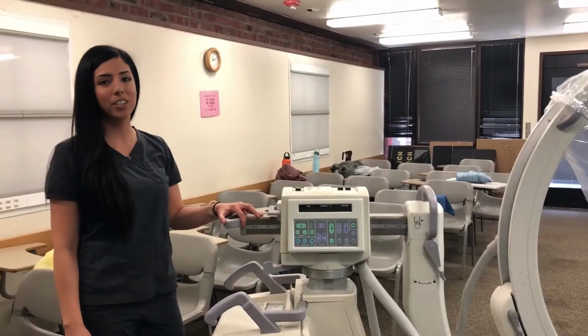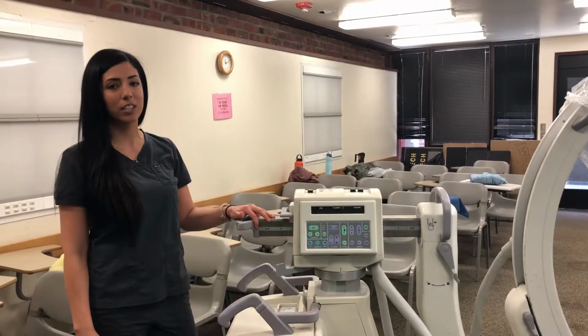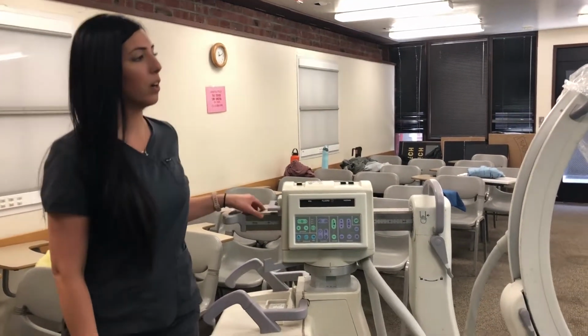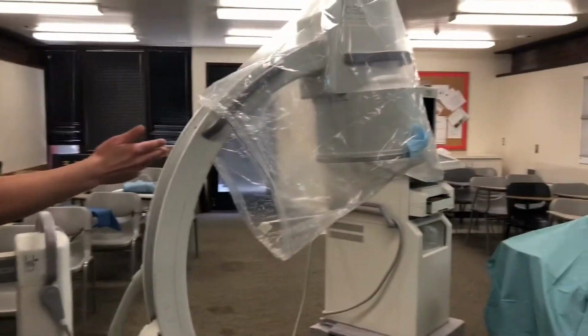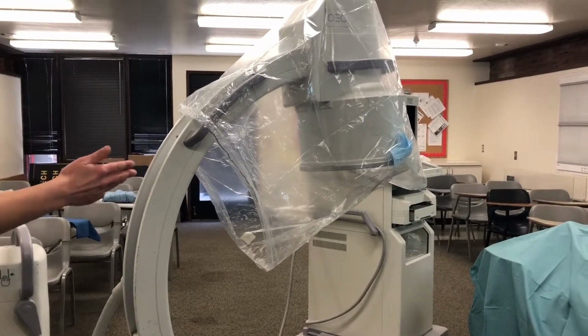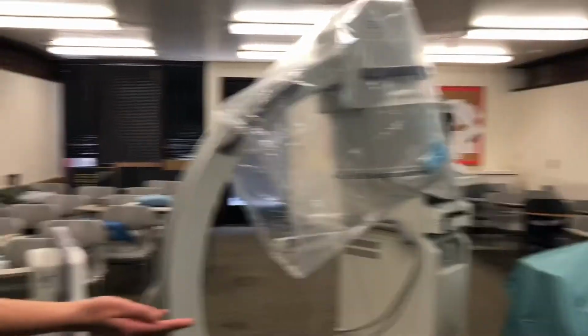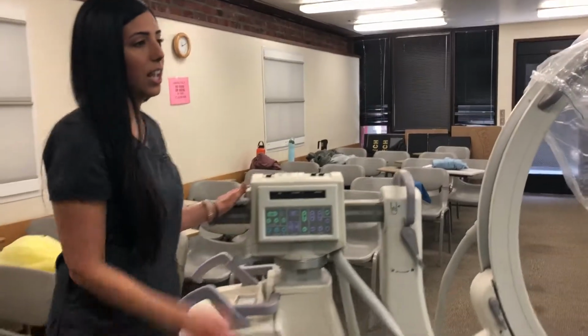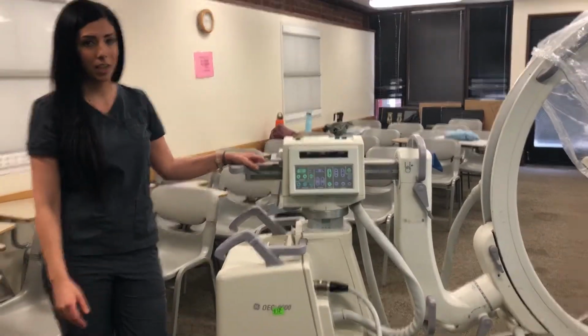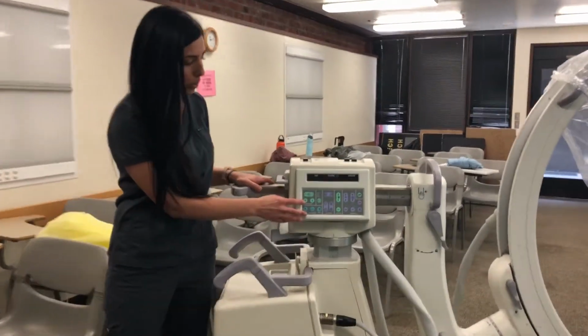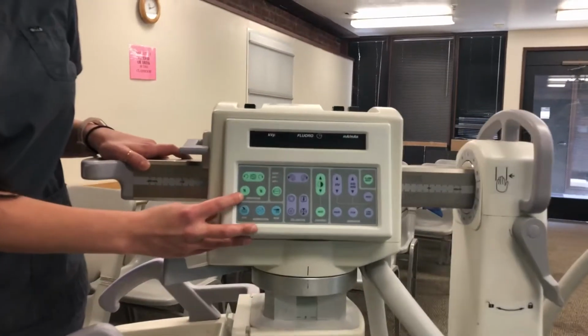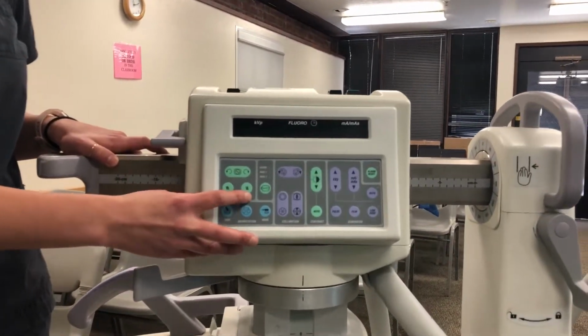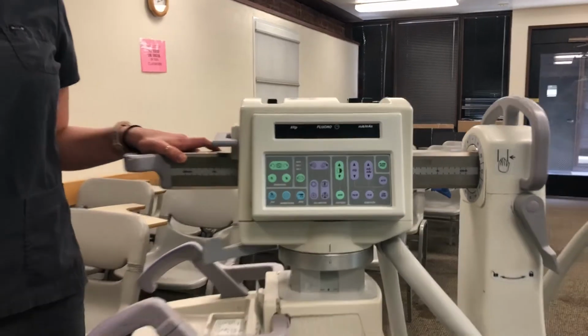So it's important when you're setting up the C-arm to make sure your orientation is correct. On most C-arms, there will be a smiley face on one side. That indicates that you're in the correct orientation if the patient is facing up and the head is on the side of the C-arm. If not, then you have these orientation buttons. This one switches right-left, and this one switches head-foot.